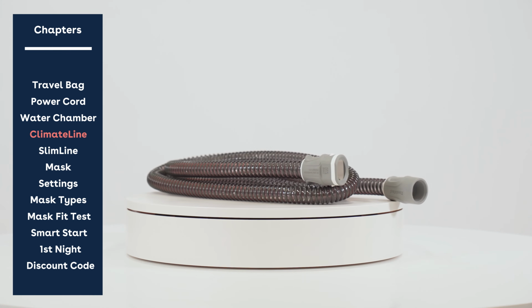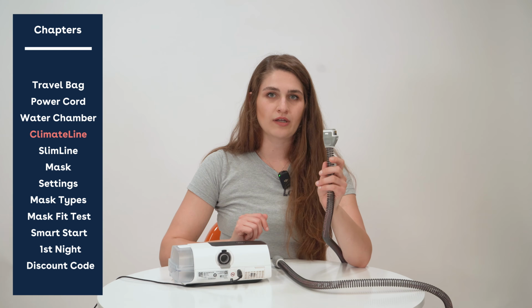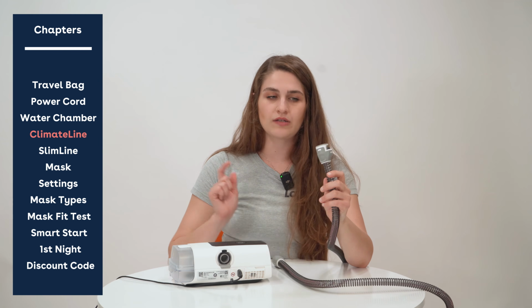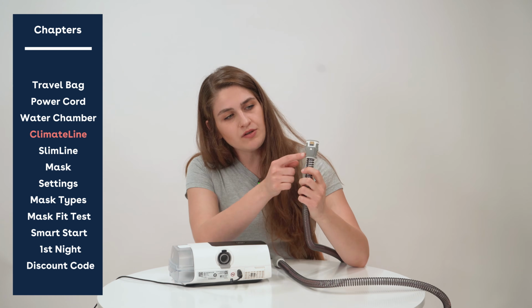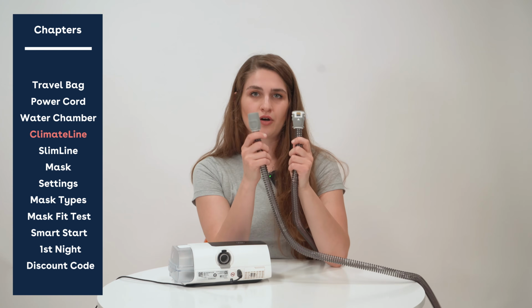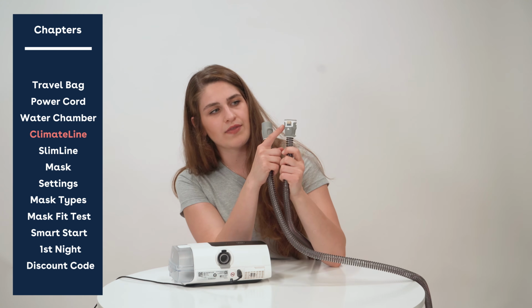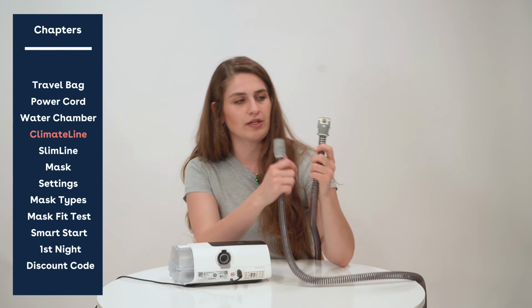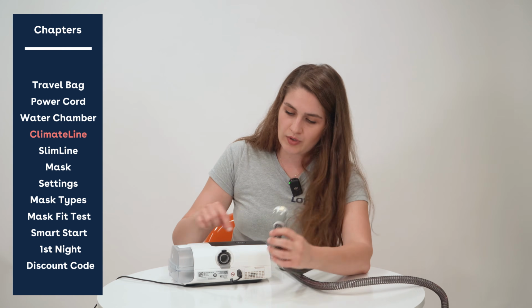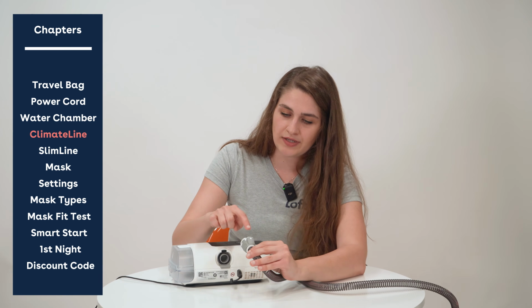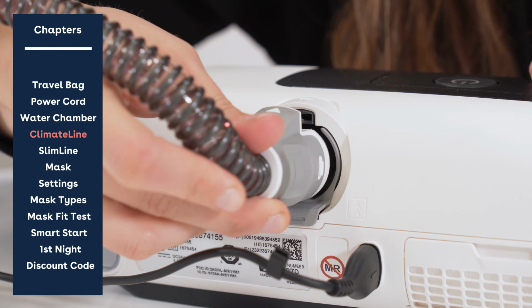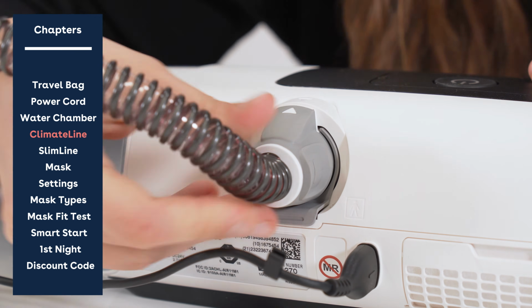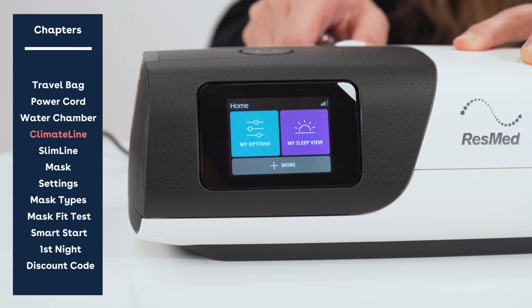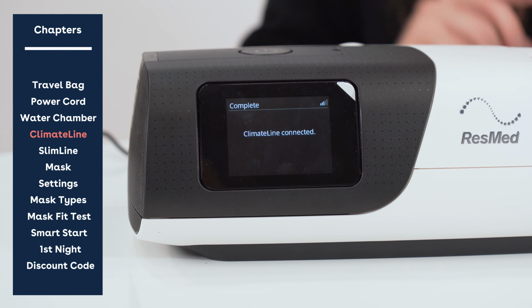So the next step will be to insert your heated tubing, or your ClimateLine heated tubing, into the back of your unit. As you can see, the ClimateLine tube's ends are different. We have one end that has an electrical chip on it with an arrow above it. We want to line up the arrows on the device and the tubing to ensure that the device can understand that you're using a heated hose. You should now see ClimateLine connected.